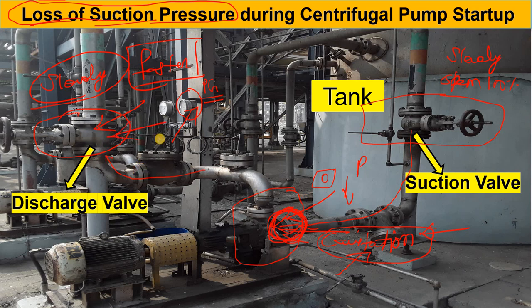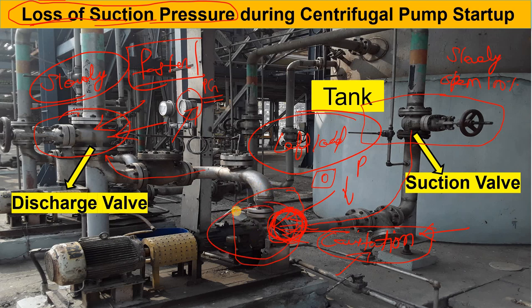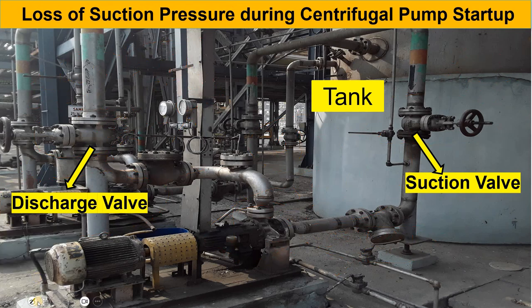If you open the discharge valve faster, the acceleration in the suction line will be greater and the velocity will be high, causing suction pressure to go low. Because of that, your pump could lose its load, run in dry condition, and the internal parts could be damaged. That's why, whenever you are starting the centrifugal pump, please throttle the discharge valve slowly initially, and then open it to 100% gradually.